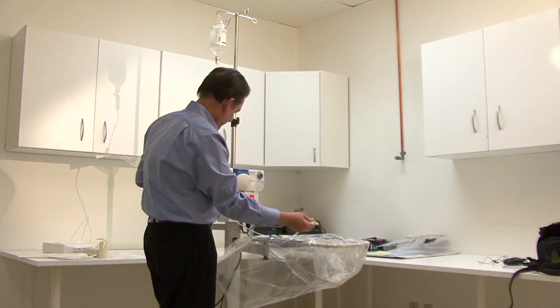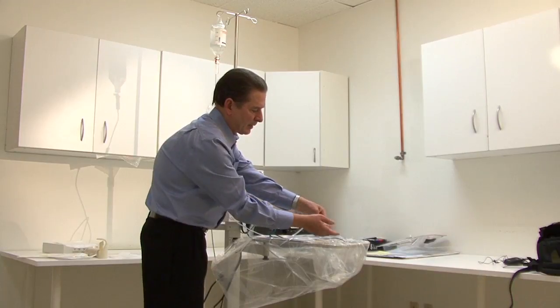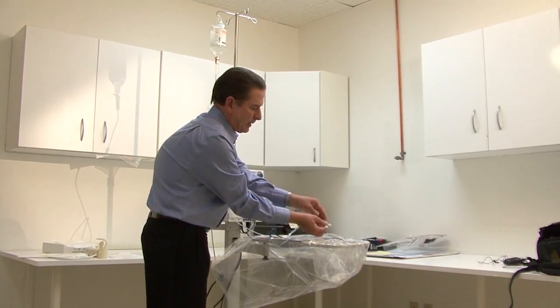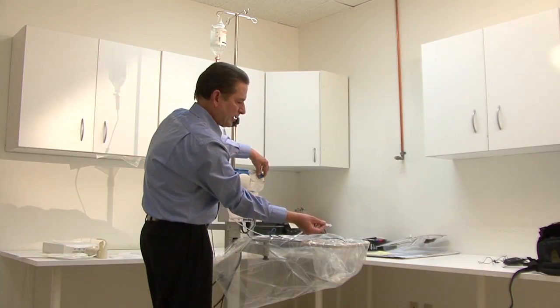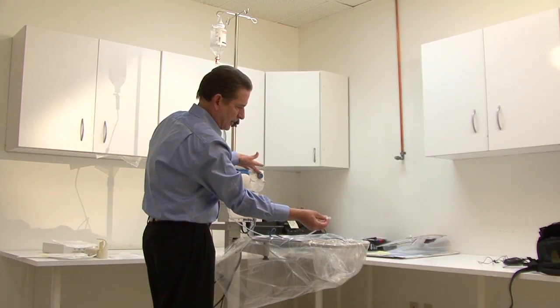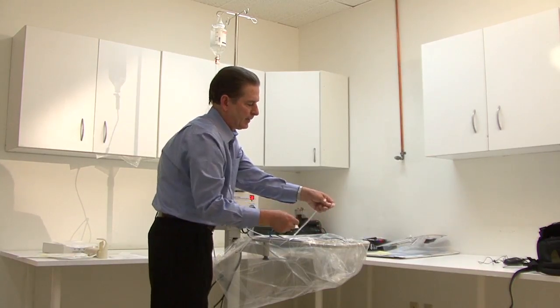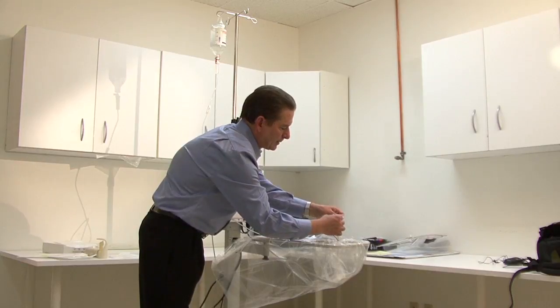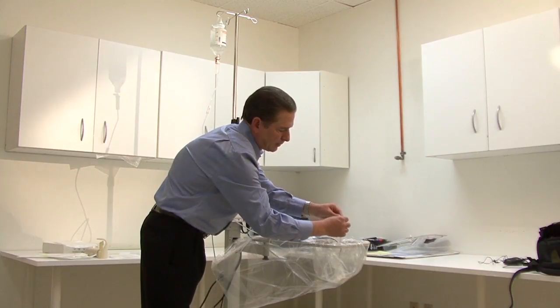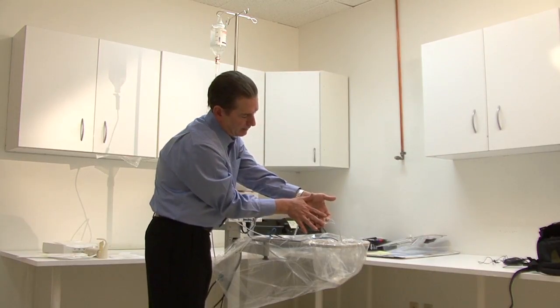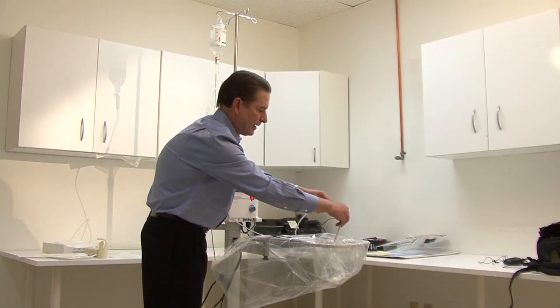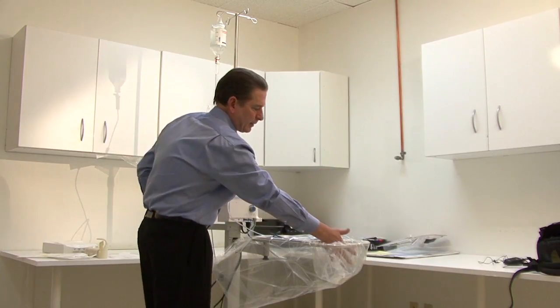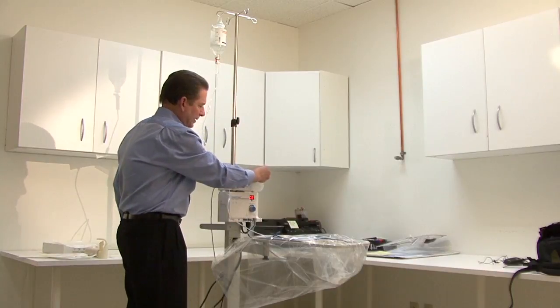So at this point, we'll just check, make sure the bubbles are flushed out. We'll have irrigation flowing from the tube. And then we can go ahead and turn off to standby. That'll stop the flow of fluid. Then we can just go ahead and connect the handpiece. And you'll notice that it only connects one way because of the male and female fittings. There's only one way we can connect it. We'll just leave the tip down in the pouch. And we'll go ahead and go back to prime.